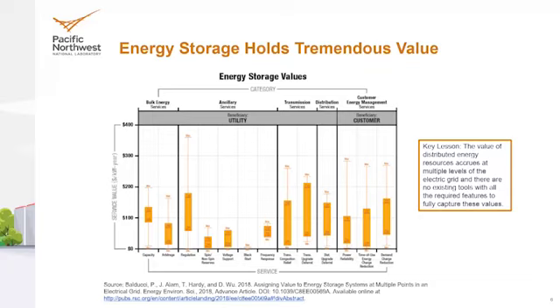Arbitrage was historically thought of as the principal value for energy storage—it makes sense that with an energy storage asset you store energy and release it later, so you'd generate enormous value through arbitrage. But in fact, we found that's one of the lowest value streams, because energy storage systems incur losses. Round-trip efficiency means that whatever comes from the grid into the energy storage system and then cycles back to the grid, you lose some of that. So a 90% round-trip efficiency means that in the round trip to the energy storage device and back, you lose 10% of that energy—it's lost in the transfer.